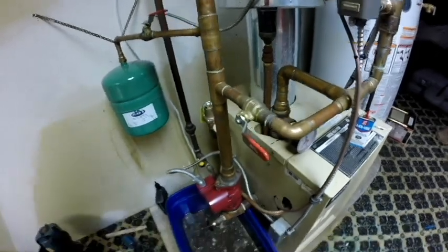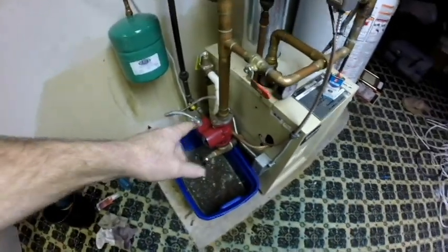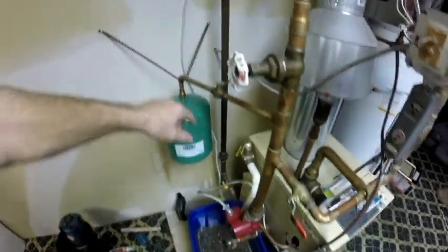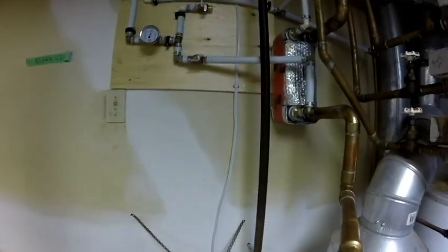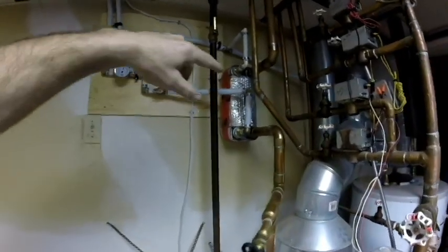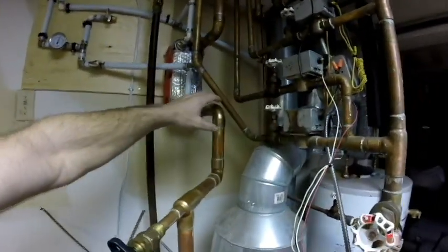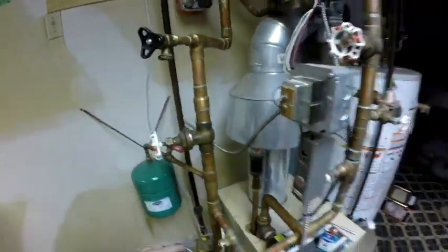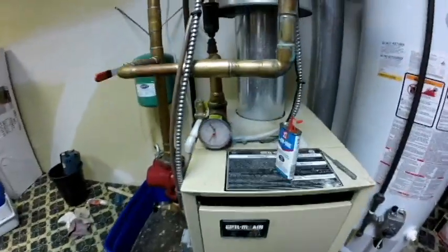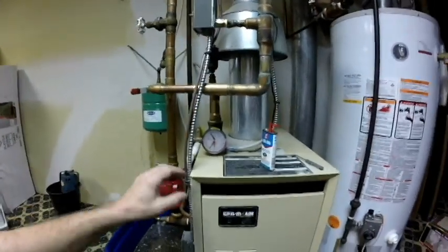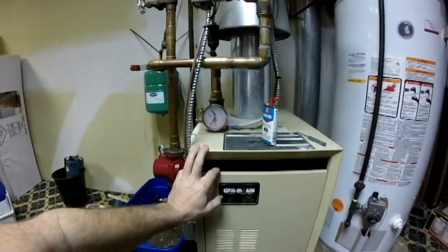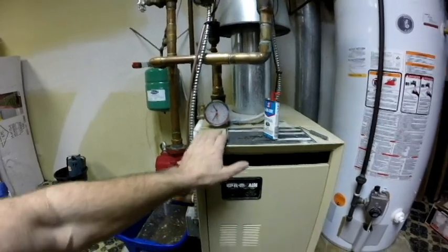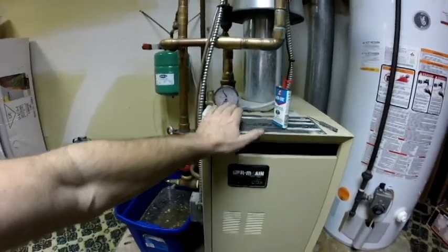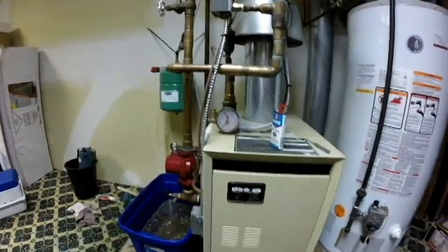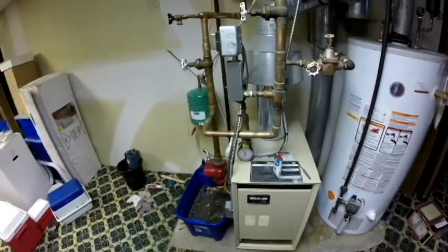Now, the system is running right now, so anytime this pump switch is on, it sends power outside to my pump to circulate the water in and out of the heat exchanger. So we're preheating the water before the boiler, and that way it keeps the temperature up on the boiler to the point that the boiler will not call for heat. Once this drops down to 130 degrees, it will then call for heat. So if there's not enough heat left in my storage tank outside, the boiler will then light up and heat the water.